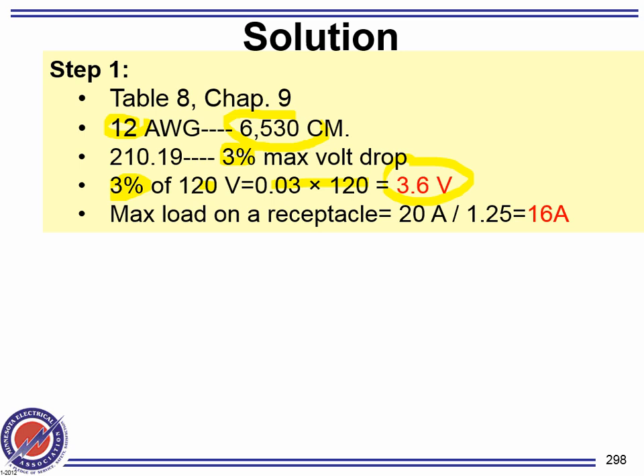3.6. Okay? And then what's your load? Your continuous load out of the breaker that you can get is 16 amps. So these are the two things that you need to find. You need to find your load, and you need to find the acceptable voltage drop. How do you find the acceptable voltage drop? It's always 3%. 3% of the source voltage. So if your source voltage is 480, just take 3% of it.